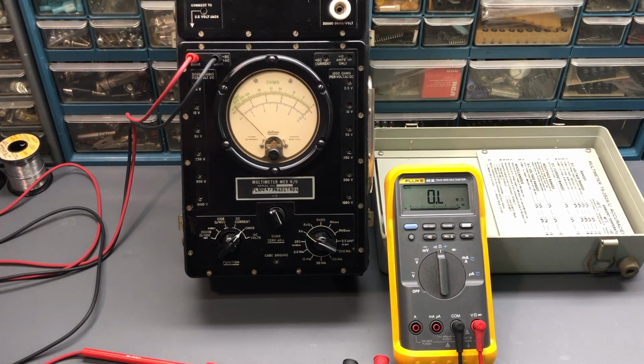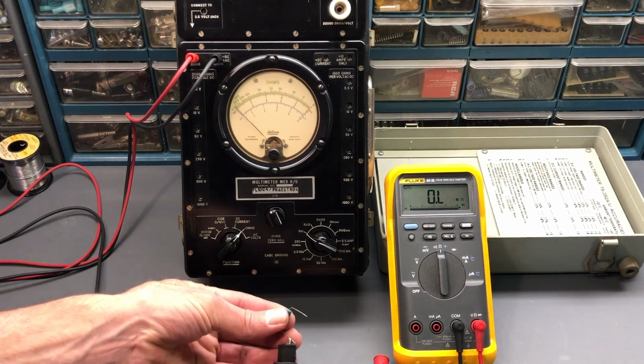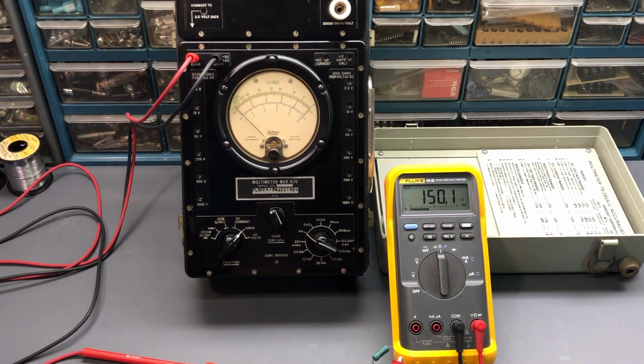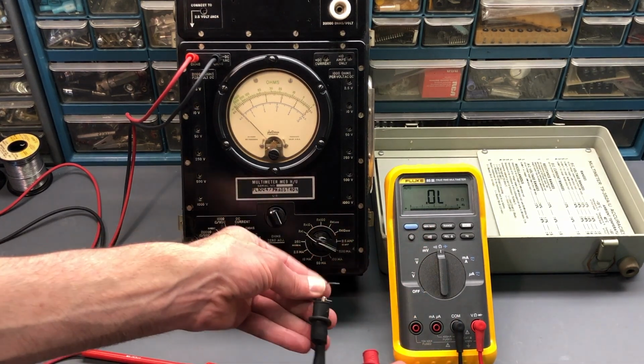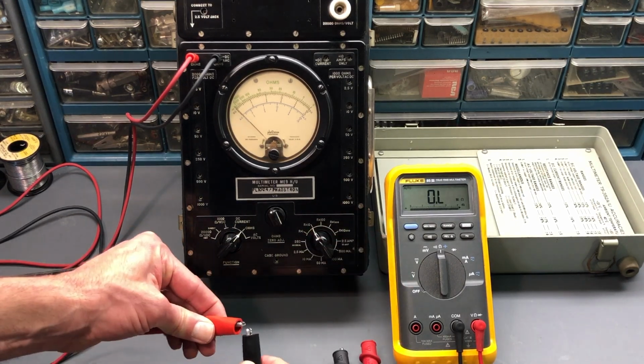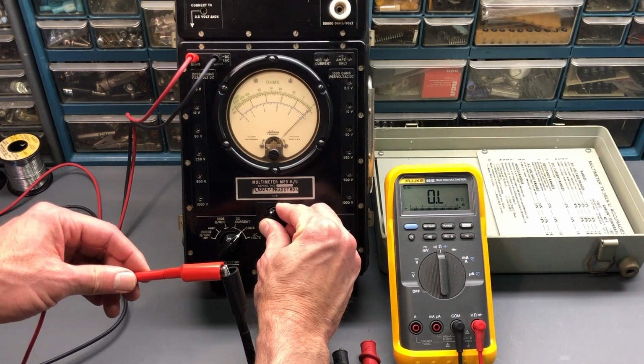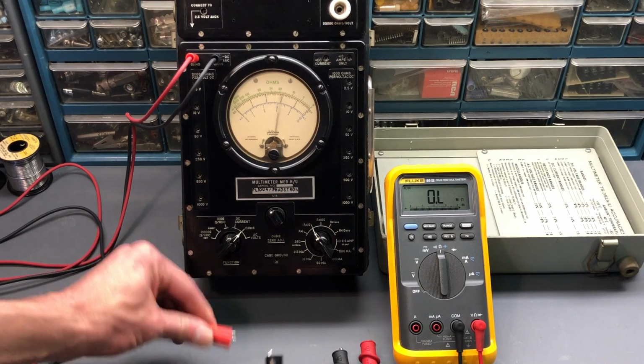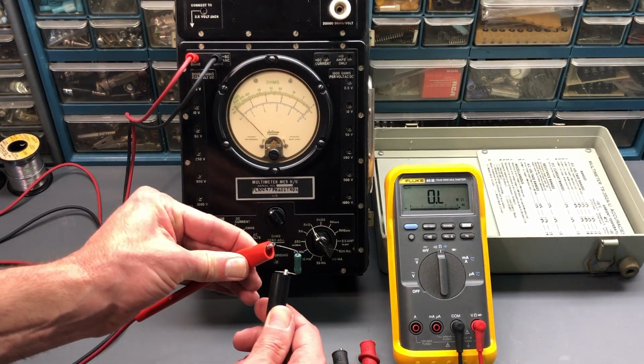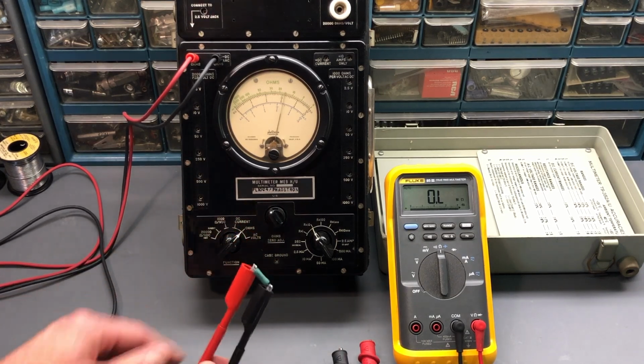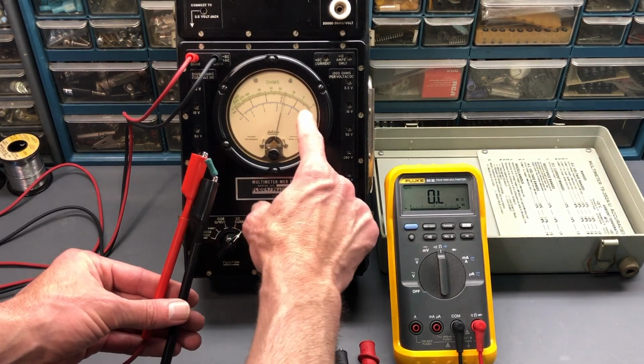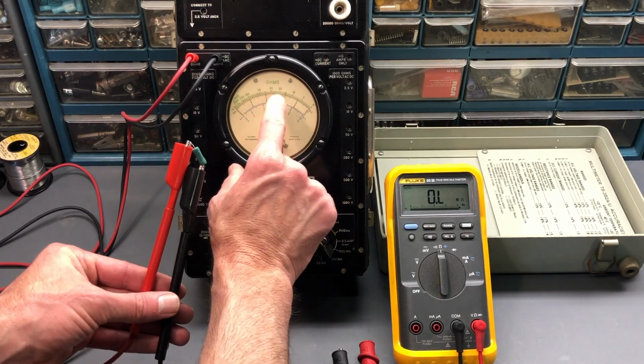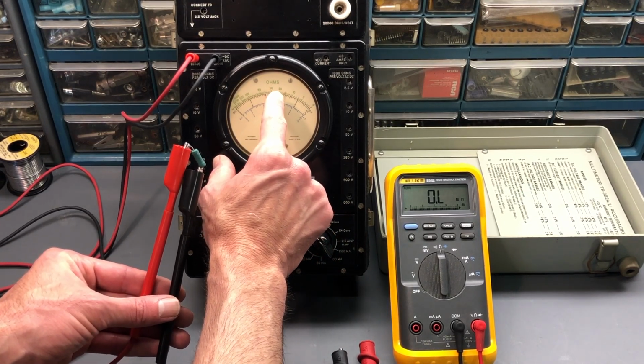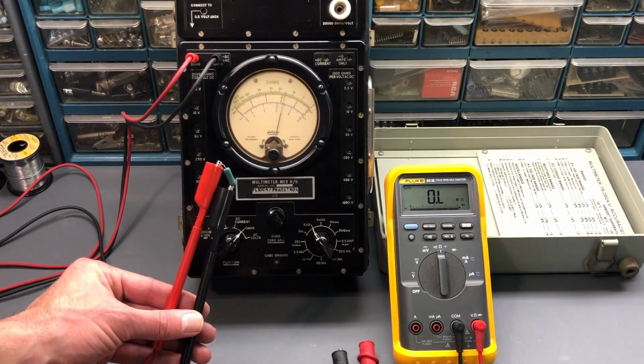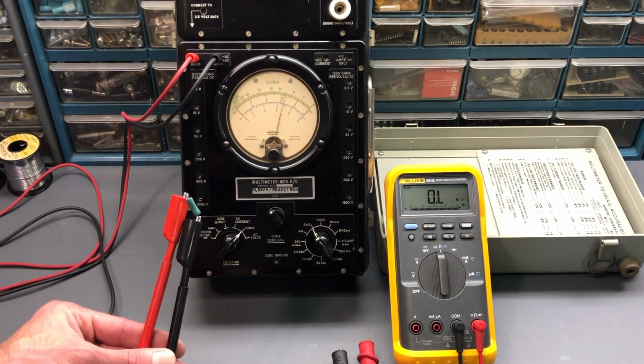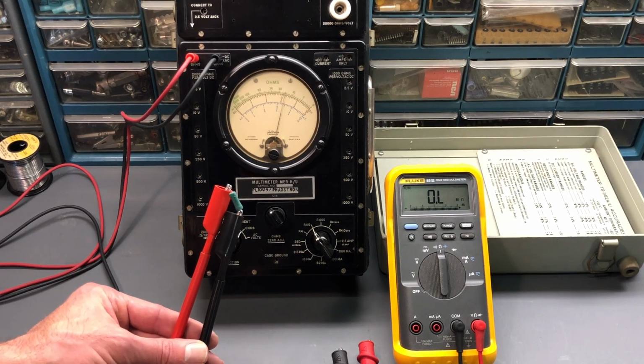So the next resistor is 150 ohms. Yep, 150, no problems there. Matches up. So we'll go to the next range, short the leads together and zero the meter. It's right on 0. Connect the resistor like so. We're on the times 10 now, so that's 0, 50, 100. This is 150 ohms, so we're right halfway between the 10 and the 20. Looks very good, maybe just the needle width past that halfway mark. Not a problem. There is a percent error that is expected with these meters, so that's looking very good. It's really, really close.